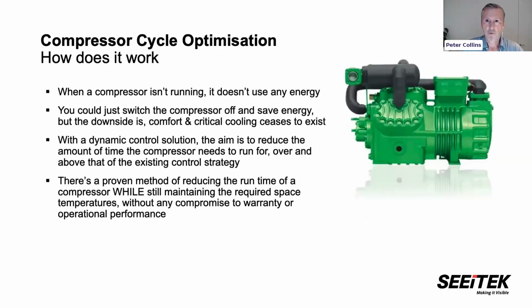So when a compressor isn't running, it doesn't use energy. You could just switch the compressor off, and the sustainability manager and the accountant will be very happy because they're saving emissions and money. But the mums and dads and the kids in the pool won't be very happy, and you'll probably be out of business before you know it. So with a dynamic solution, the aim is to reduce the amount of time that the compressor runs for, or that it's loaded for, over and above the mechanical control that has been supplied with that system.